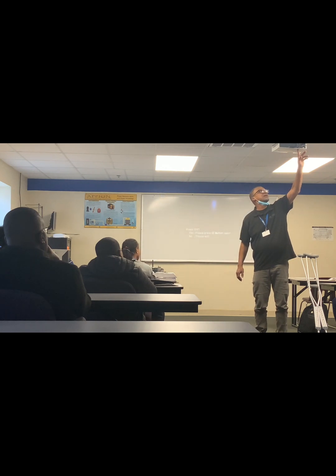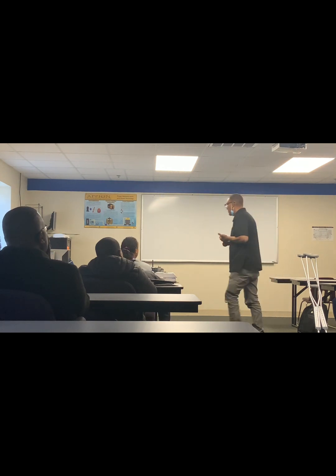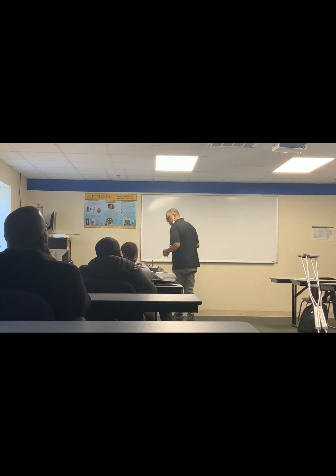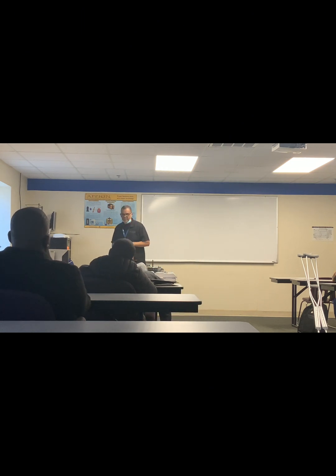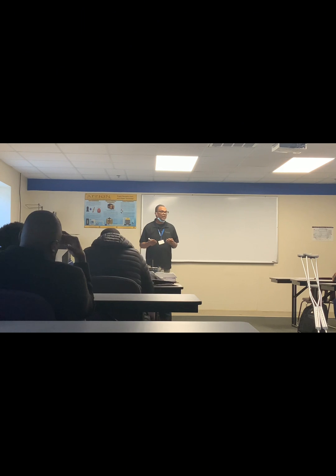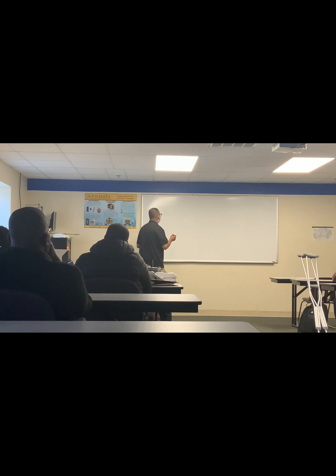So that's just a little stink piece on the difference between motors. ECMs are here to stay, as well as variable refrigerant flow, which you haven't heard a lot about. Modulating motors keeps a motor from running 100% when not necessary. The ones running 100% will cool, will work, but they use a lot of energy, and energy use is a cost to you and the customer. So ECM motors, variable refrigerant flow compressors.